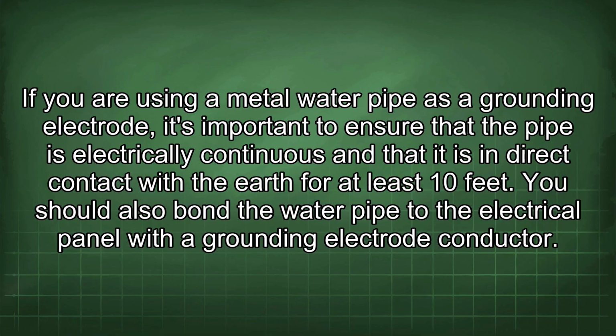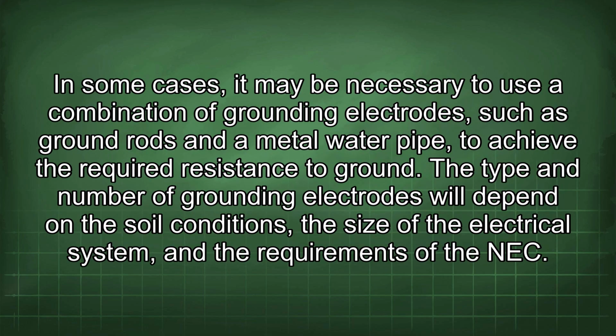If you are using a metal water pipe as a grounding electrode, it's important to ensure that the pipe is electrically continuous and that it is in direct contact with the earth for at least 10 feet. You should also bond the water pipe to the electrical panel with a grounding electrode conductor. In some cases, it may be necessary to use a combination of grounding electrodes, such as ground rods and a metal water pipe, to achieve the required resistance to ground. The type and number of grounding electrodes will depend on the soil conditions, the size of the electrical system, and the requirements of the NEC.